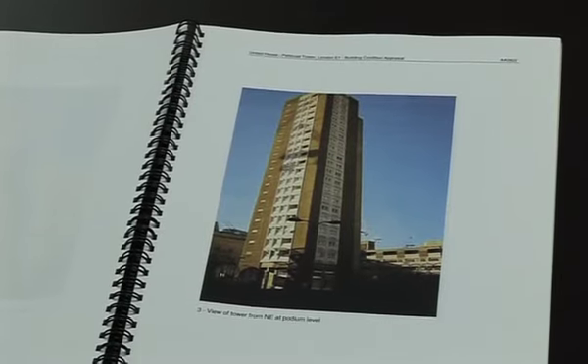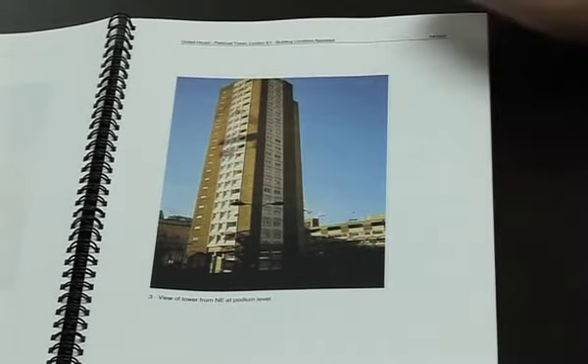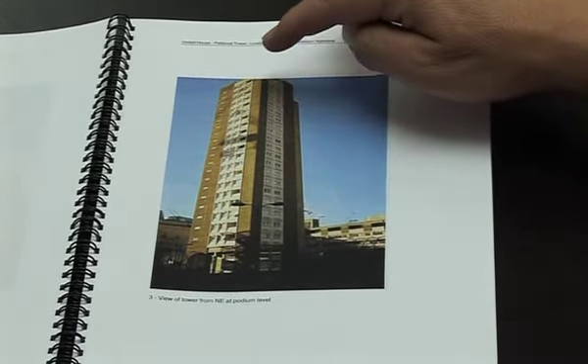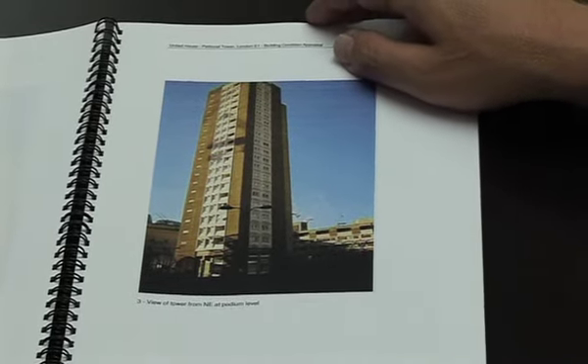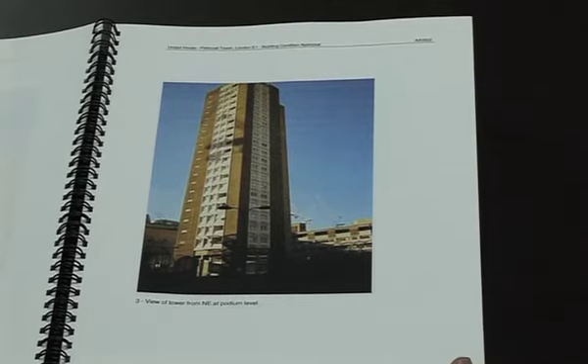Working with PHPP, we have established that we can approach the EnerPHit standard relatively straightforwardly, and the form of the building as a tower block helps in that most flats only have 2 or maximum 3 exposed sides. We use the PHPP software to input the usual floor areas, the U values of the windows, the psi values of the cold bridging around those windows. We've based it on a Passive House certified heat recovery ventilation system.